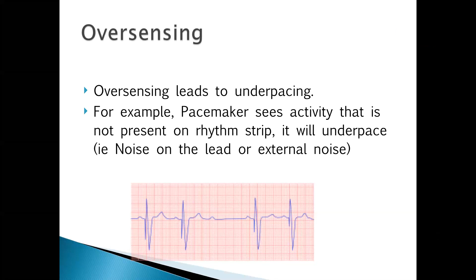Exactly. So again, if you notice, there's no atrial spikes anywhere. But you know this has to be a dual chamber device because it's tracking appropriately, right? So the atrial lead is definitely sensing. You don't know if the atrial lead is pacing, but you definitely know the atrial lead is sensing because every A sensed is followed by a V paced, except in the middle where you don't see a ventricular paced. So again, you went through the same process of seeing A sense, V paced, A sense, V paced, and figuring out what the device is seeing. And then you figured out, hey, there's a problem with the ventricular lead. Make sense? Let's talk about this for a bit longer.